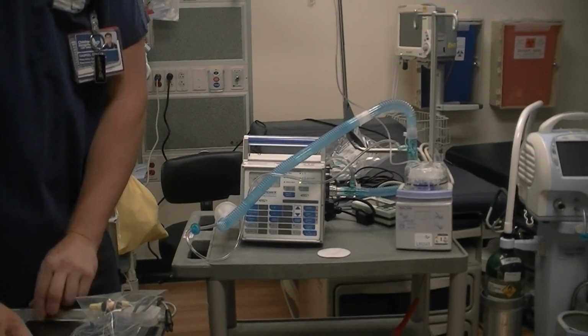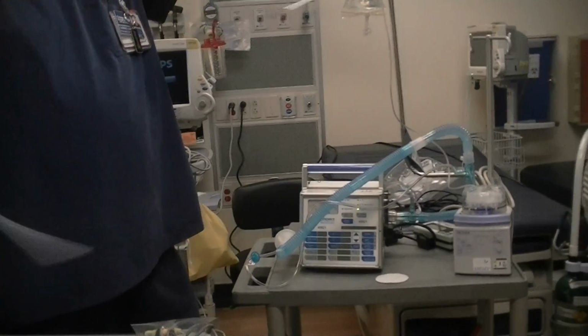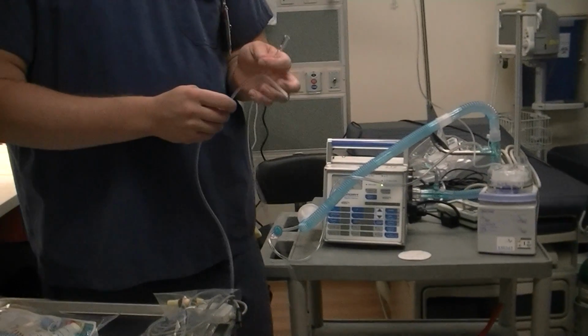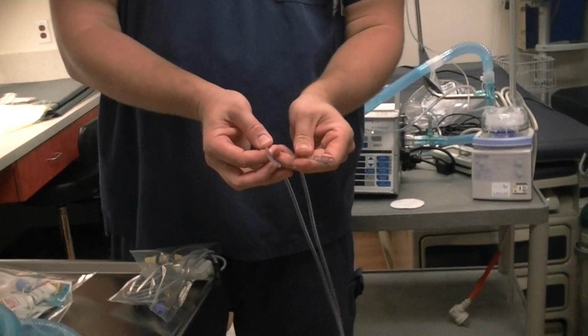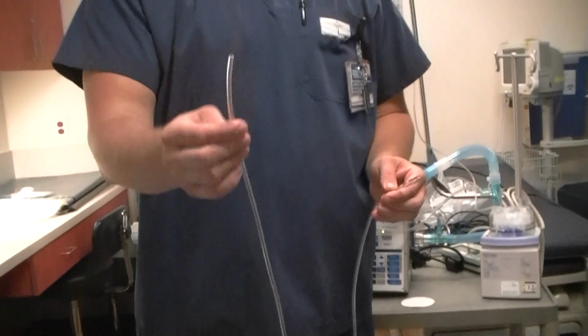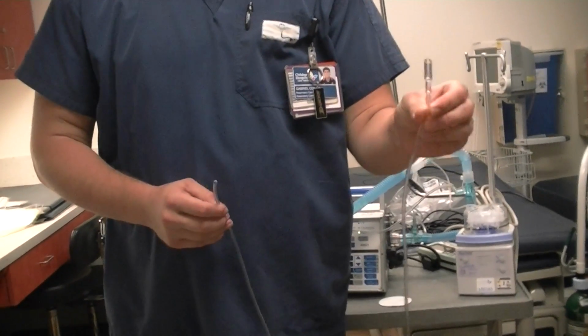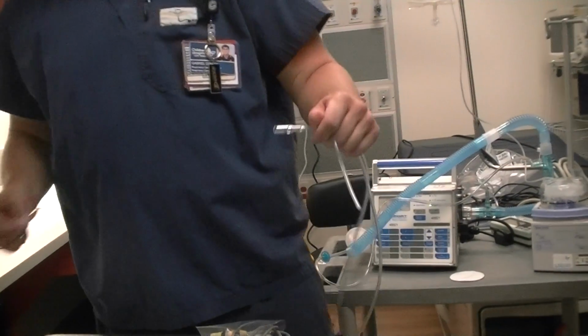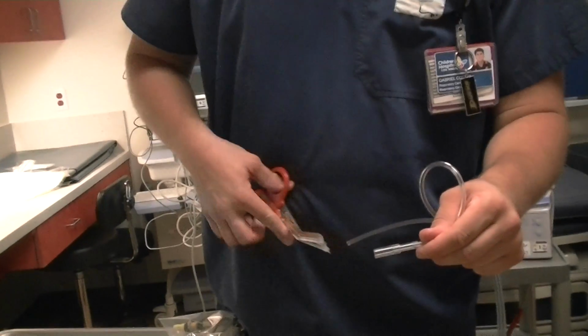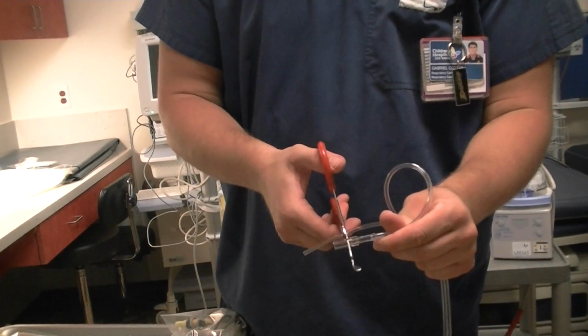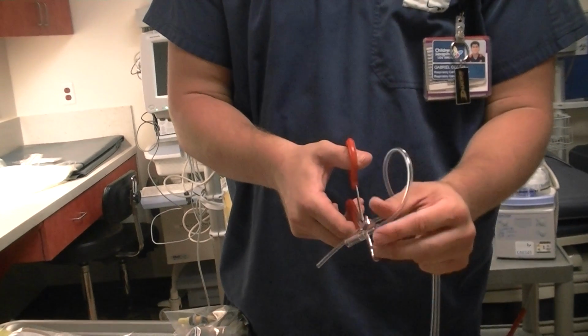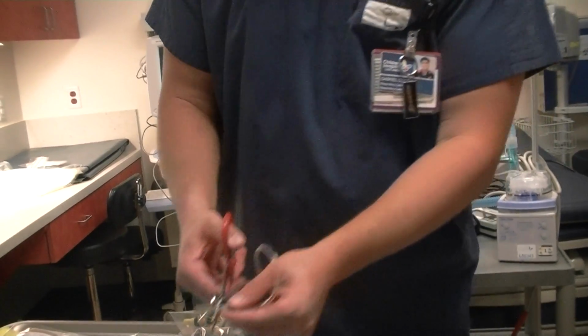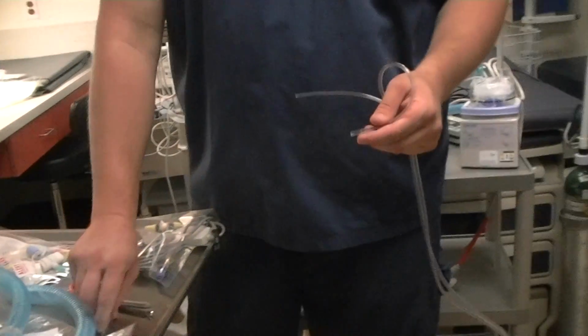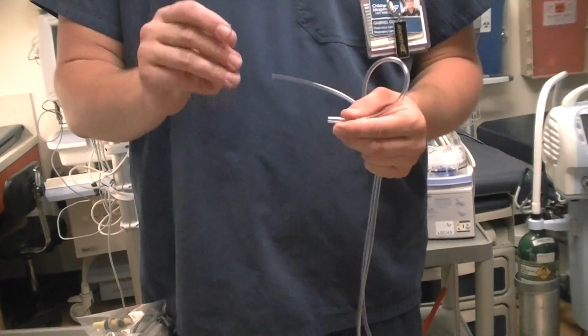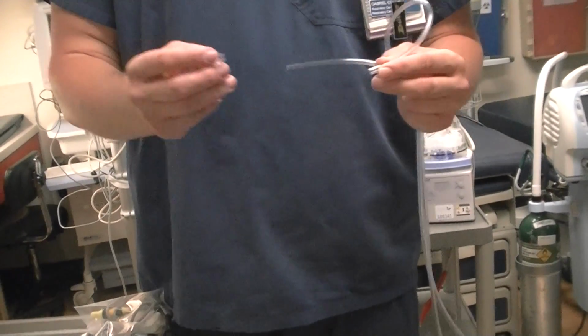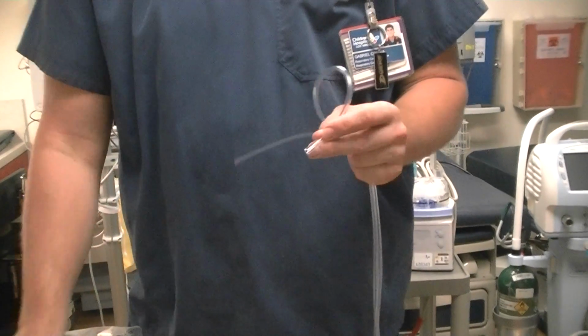Okay? Next, you're going to grab your exhalation line, and you'll see it has two ends. This one is proximal to the patient. This one's going to be on the ventilator. What you want to do is cut. You have 3 steps here: 1, 2, and 3. You want to cut at the first step down. So your largest step, you want to cut that piece off. If you don't cut this piece off, you won't have a great seal on your exhalation side, so you'll be prone to a lot of leaks or disconnections.